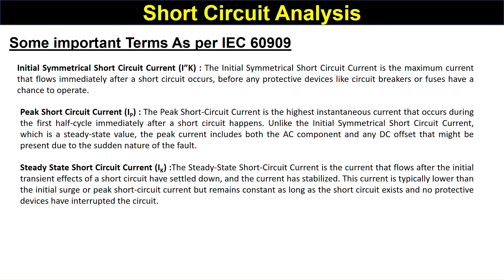The Steady-State Short-Circuit Current is the current that flows after the initial transient period of the short circuit has settled down. This current is typically lower than the Initial Symmetrical or Peak Short-Circuit Current but remains constant as long as the short circuit exists and no protective device has interrupted it. Once the short circuit is not removed, the current attains a fixed steady-state value that remains constant until the short circuit is cleared.